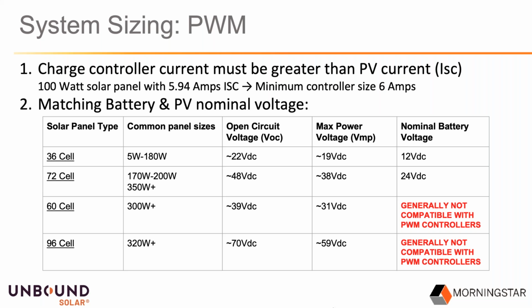If you're trying to charge a 24 volt battery at that voltage, depending on the battery type, your 24 volt battery needs to charge at about 28 to 30 volts. If it's a flooded battery, you might need to equalize at about 32 volts. So already we have about 31, 32 volts coming in from solar, and that's before we lose anything to heat or voltage drop. So potentially only 30 volts coming in through solar.